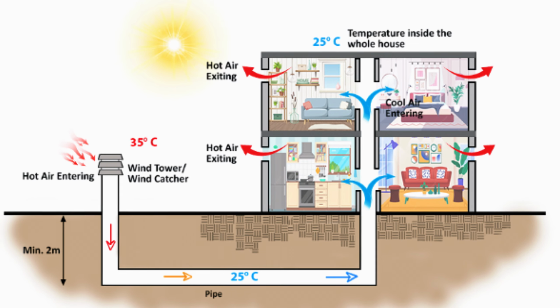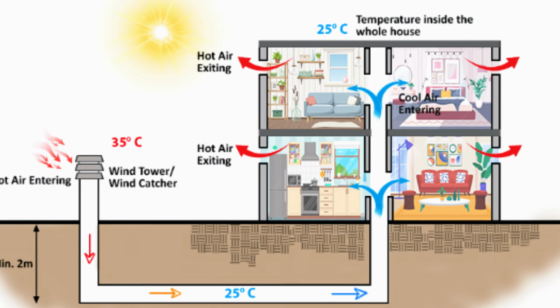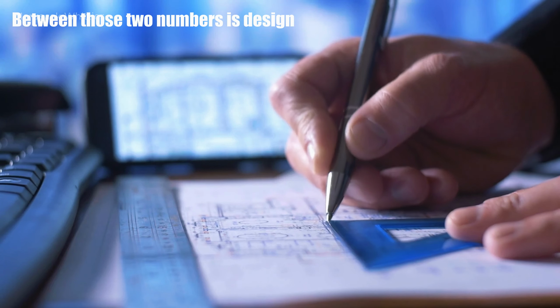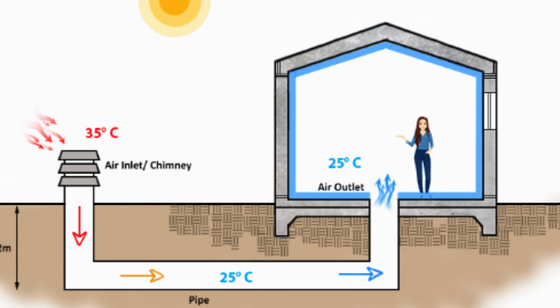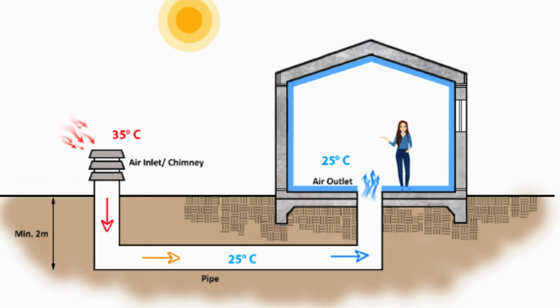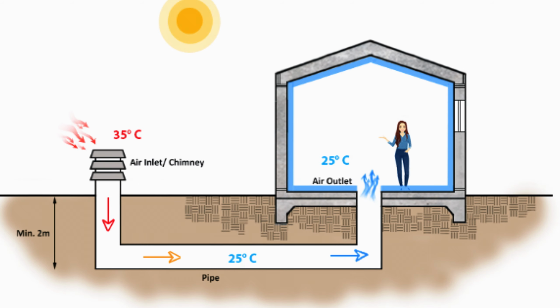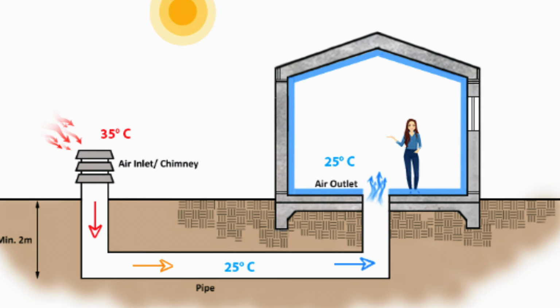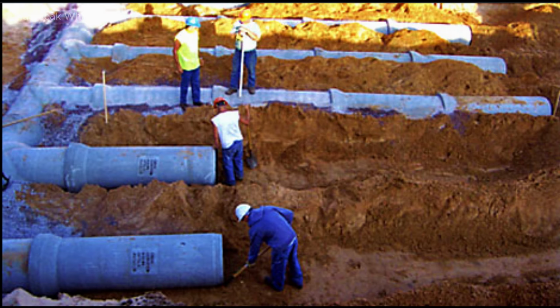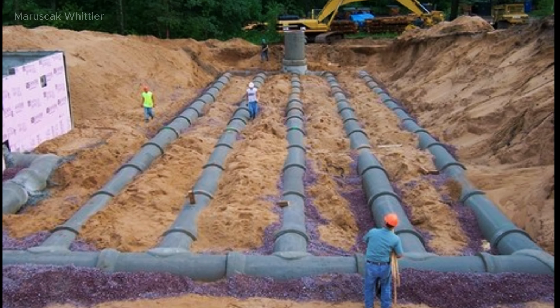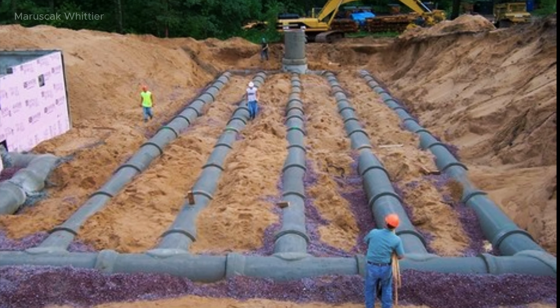But this is where many viral claims become misleading. Ground temperature and room temperature are not the same thing. Between those two numbers is design. The air coming out of the pipe depends on pipe length, burial depth, airflow speed, soil type, soil moisture, groundwater, pipe material, and condensation control. In the right conditions, this system can pre-cool incoming air and reduce the load on mechanical cooling. It should not be described as a guaranteed way to make every home cold.